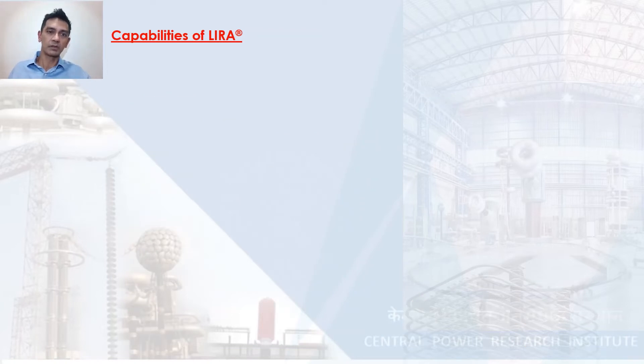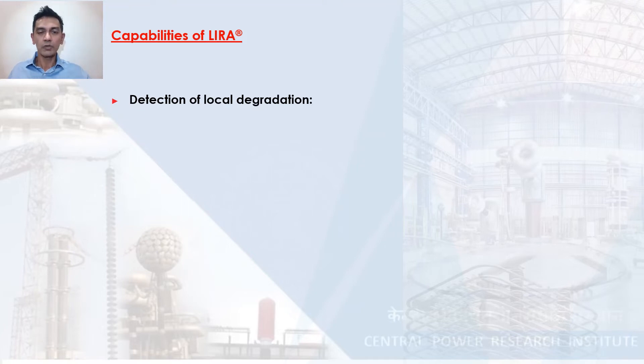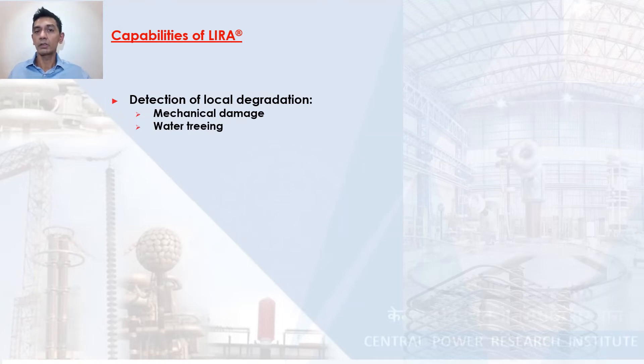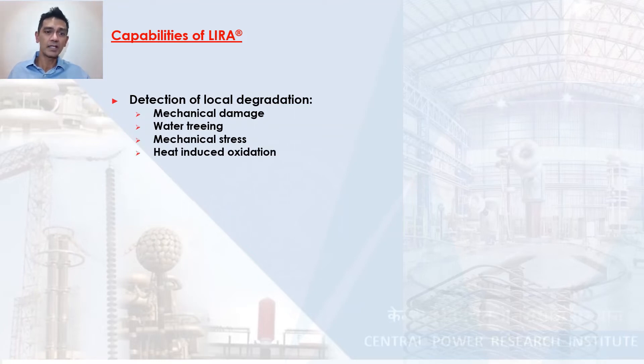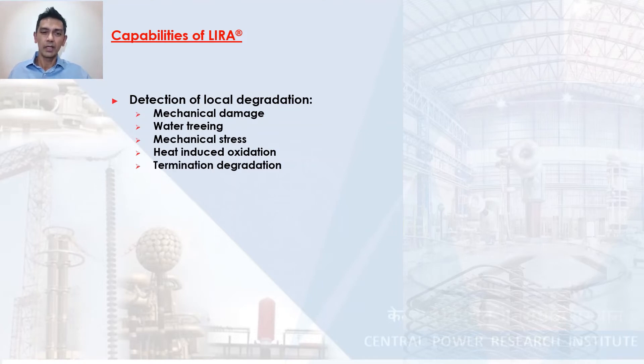What are the capabilities of the Lira system? With regards to finding localized defects, it can pick up mechanical damage, the presence of water trees in a cable, mechanical stress points, heat-induced degradation or oxidation, and defects in the cable terminations.